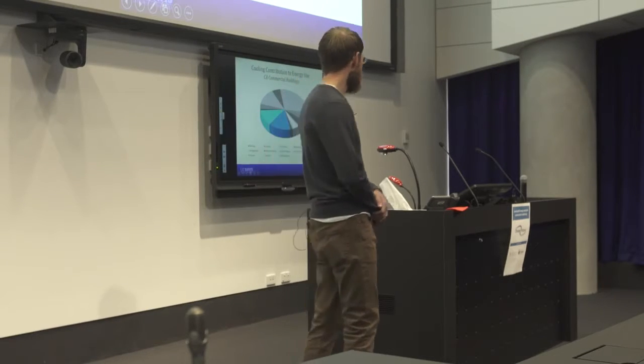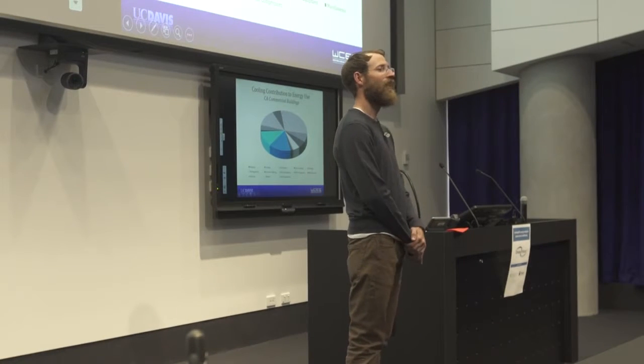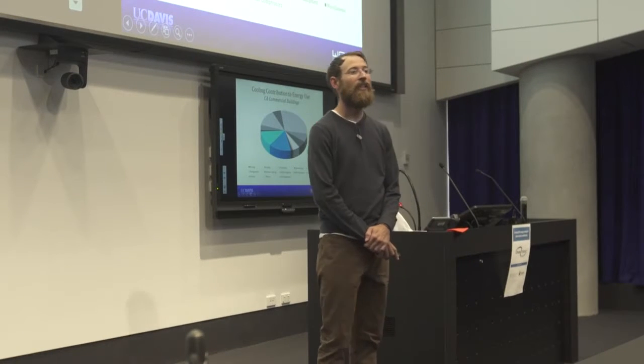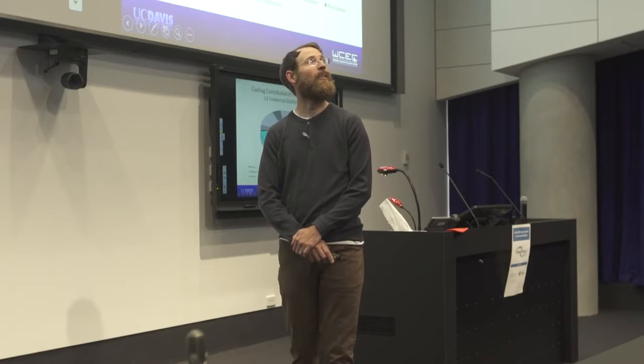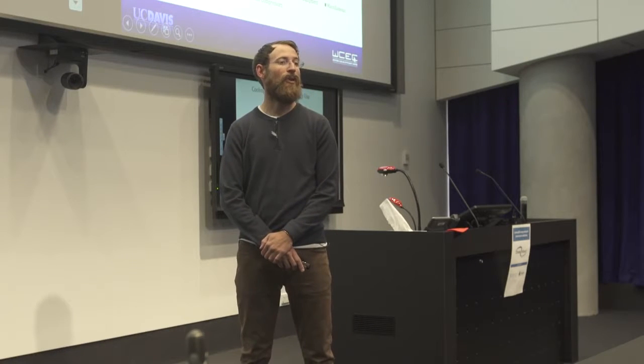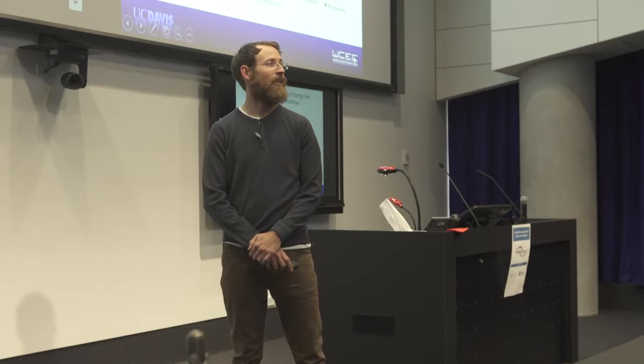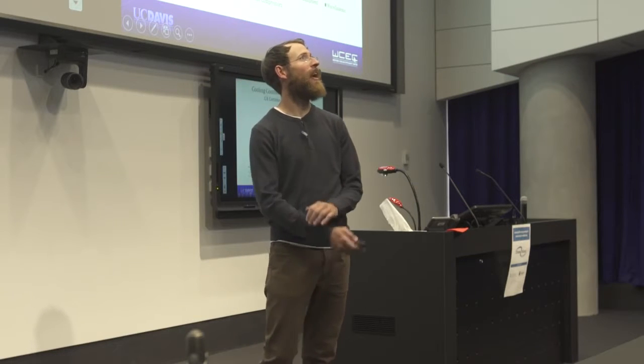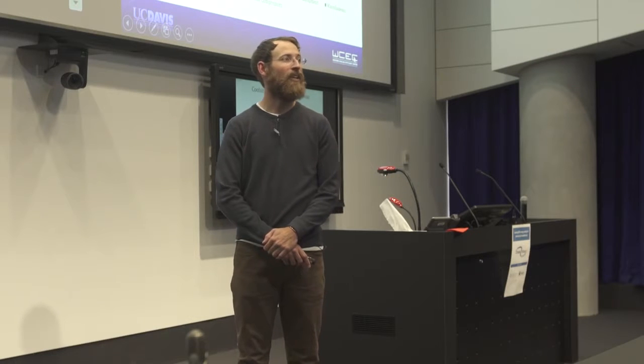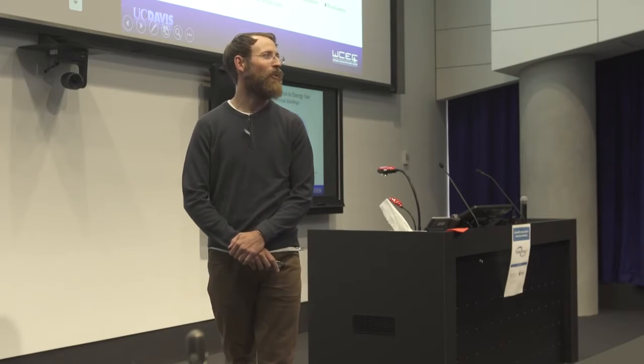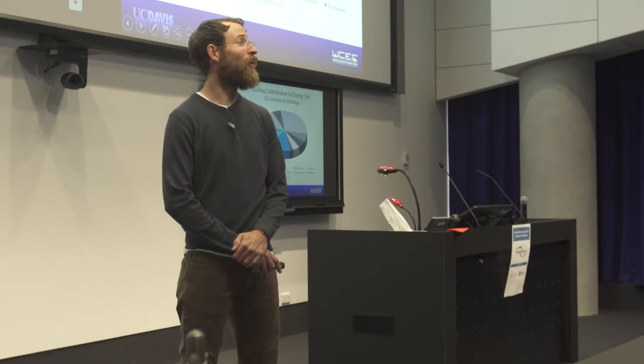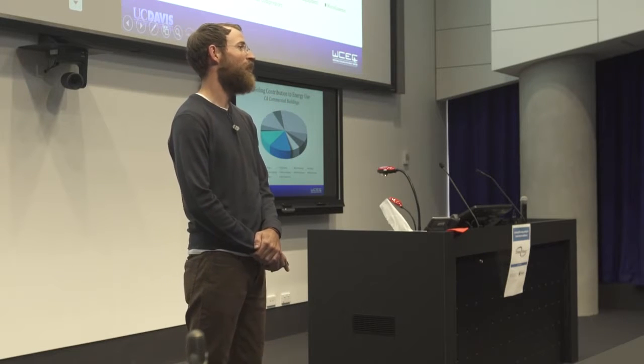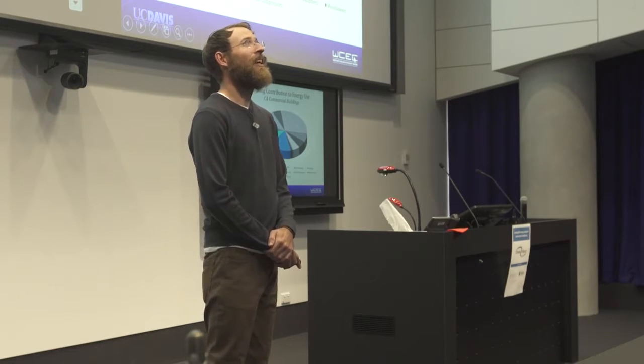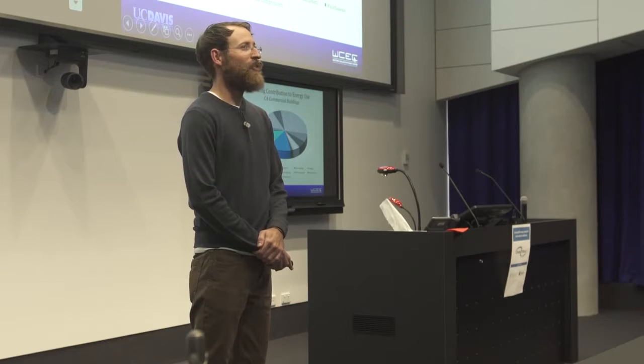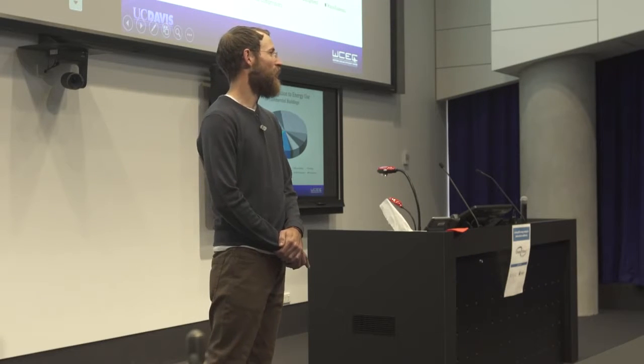So here's the real motivation. Cooling and ventilation in California commercial buildings takes up about 25% of our annual energy consumption. It's a major fraction, and I've highlighted those two pieces in this pie on the slide, not to say that the other pieces aren't important, but to show you what a large fraction cooling and ventilation take up, and to point out the fact that a lot of those other end uses are actually starting to decrease.